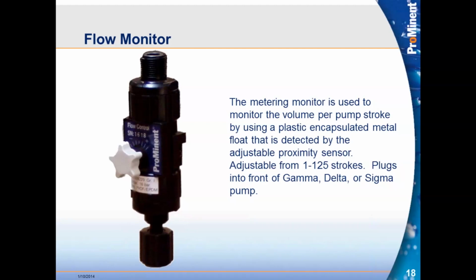The default number on that is 8 strokes without feedback, and I would probably recommend, so that you don't get nuisance alarms, you probably shouldn't go below that number 8. It seems to be a pretty solid number. But we can go as high as 125. Some people will ask us if we can extend that beyond 125. We can't in the programming of the pump.